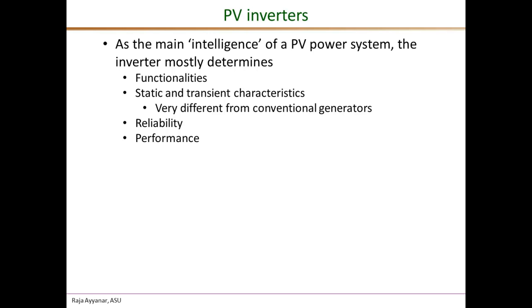The steady state and transient characteristics of the PV power system depend on how the controllers inside the inverter have been designed, and these characteristics can be very different from those of conventional power plant generators — both in positive ways and in negative ways, for example in terms of the fault current characteristics and the response during system contingencies.